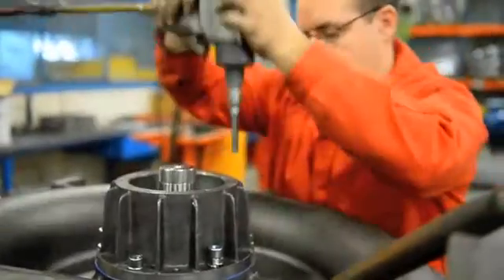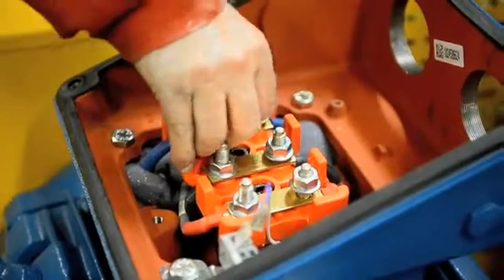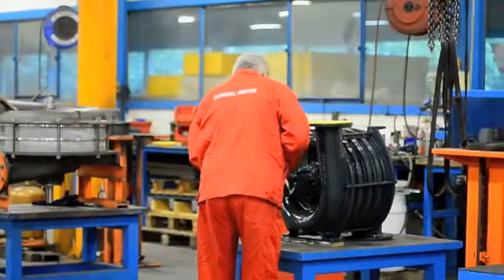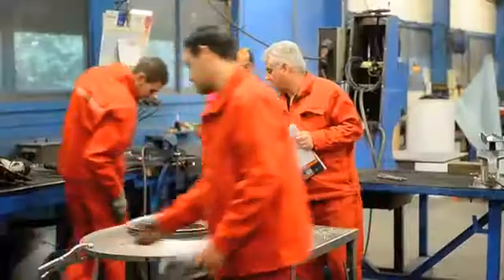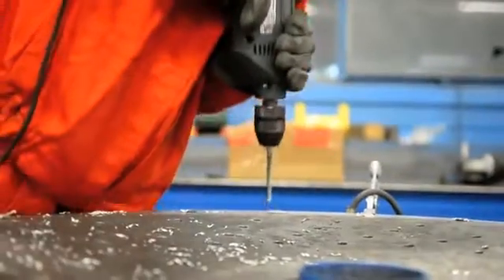Impeller assembly. The impellers are cast or fabricated in treated aluminium alloy. All impellers are individually statically balanced, then keyed to a ground carbon steel shaft. The complete rotor assembly is dynamically balanced to ensure a normal vibration amplitude of the blower of 2.5 millimeters per second RMS.